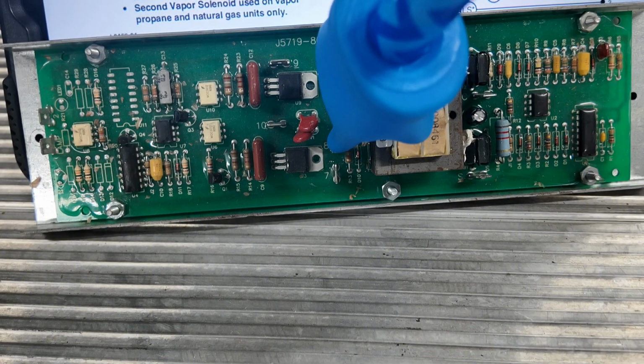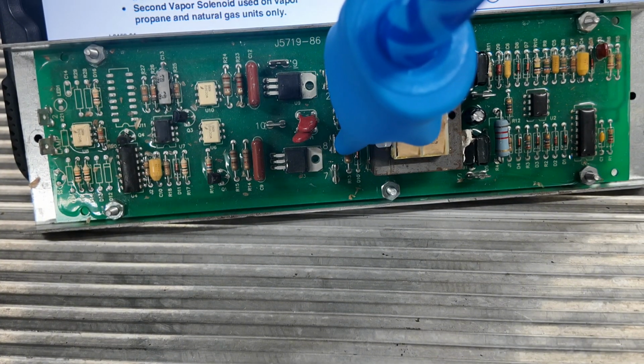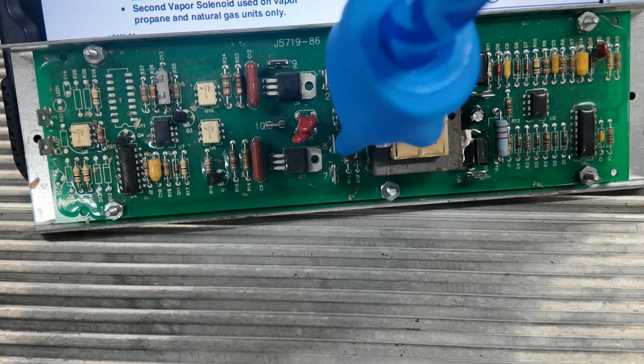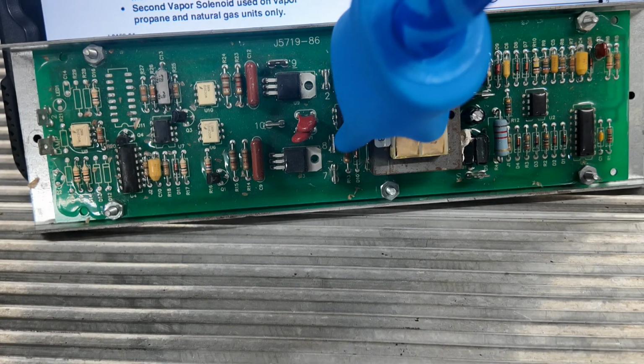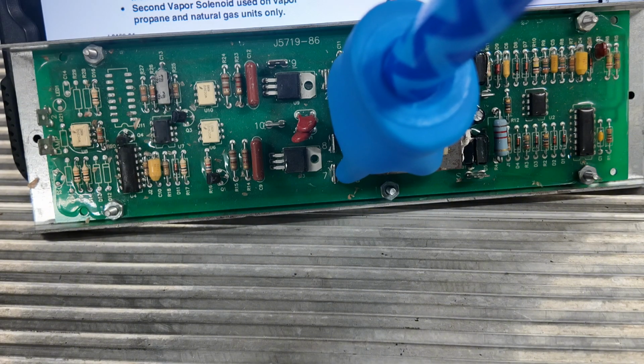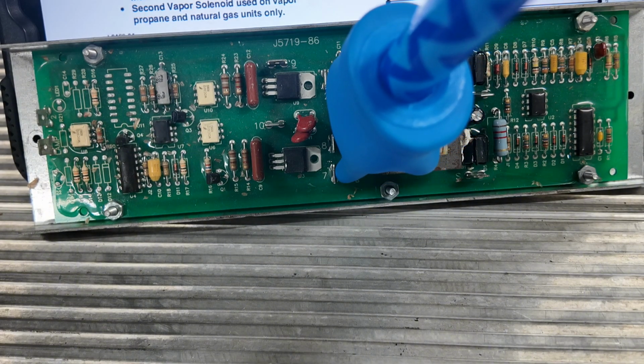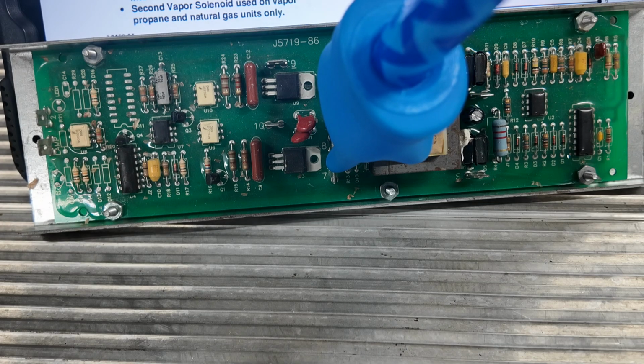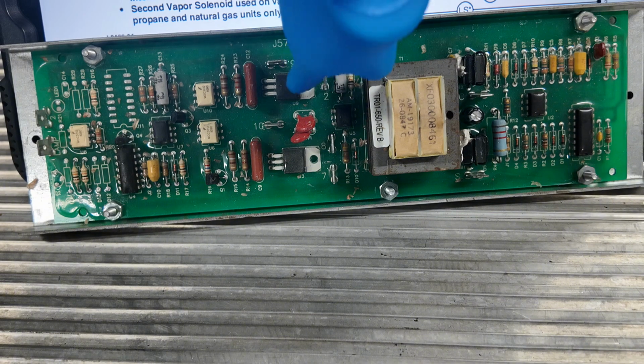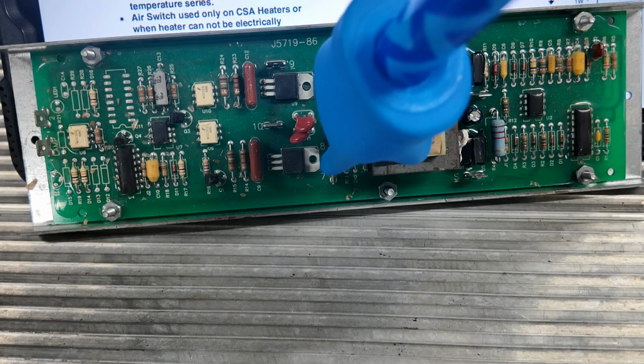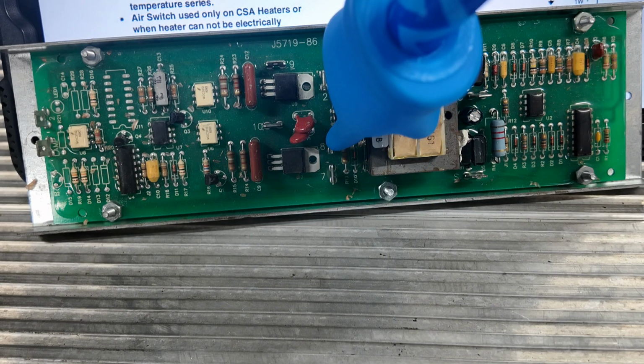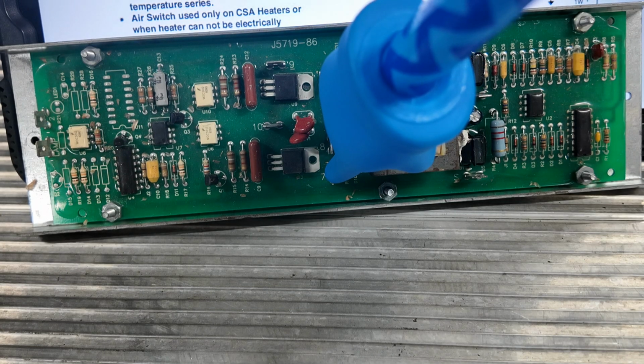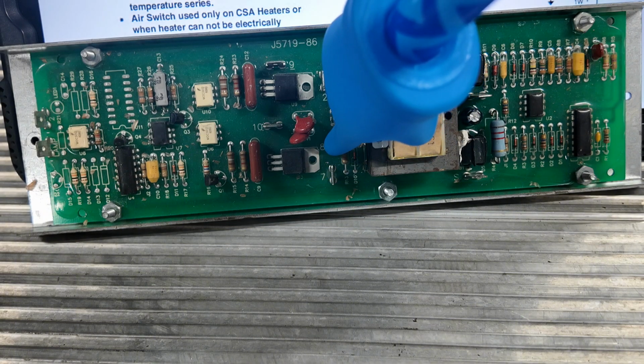8 is your thermostat power, where the thermostat turns the power off and on to terminal 8. 7 is your main power. When you put power to 7, purge time starts. If you put power to both of these at the same time, the purge time will start, and when the purge time is up, you get voltage out on 9 and 10. If you put power to 7 and not to 8 and let your purge time complete, then when you put power to 8, it will instantly power 9 and 10.